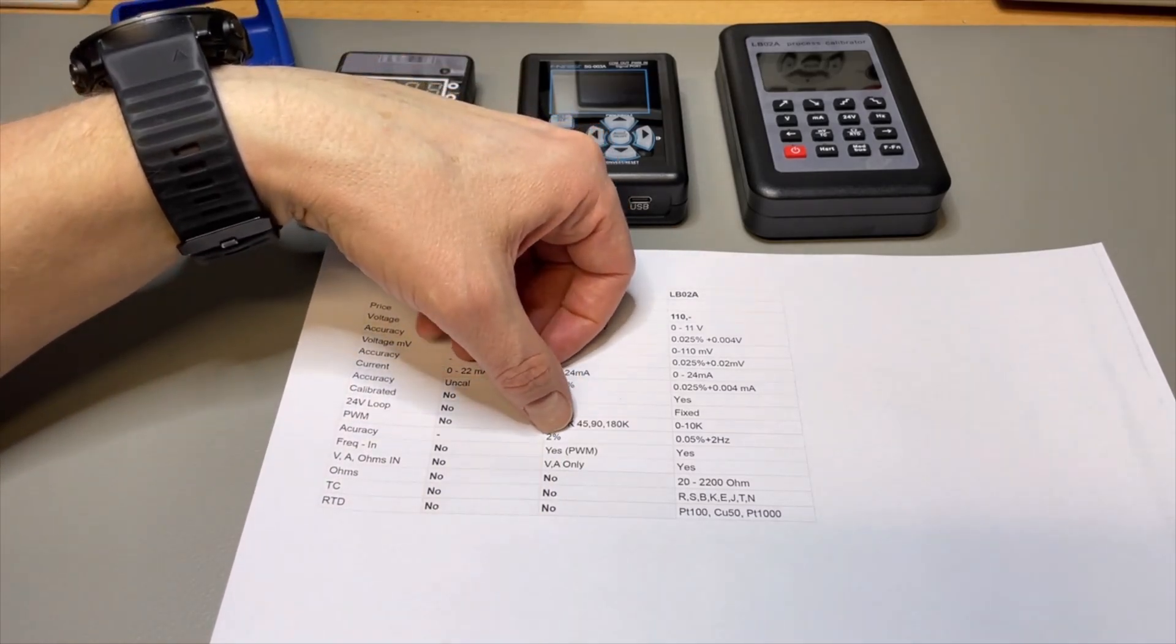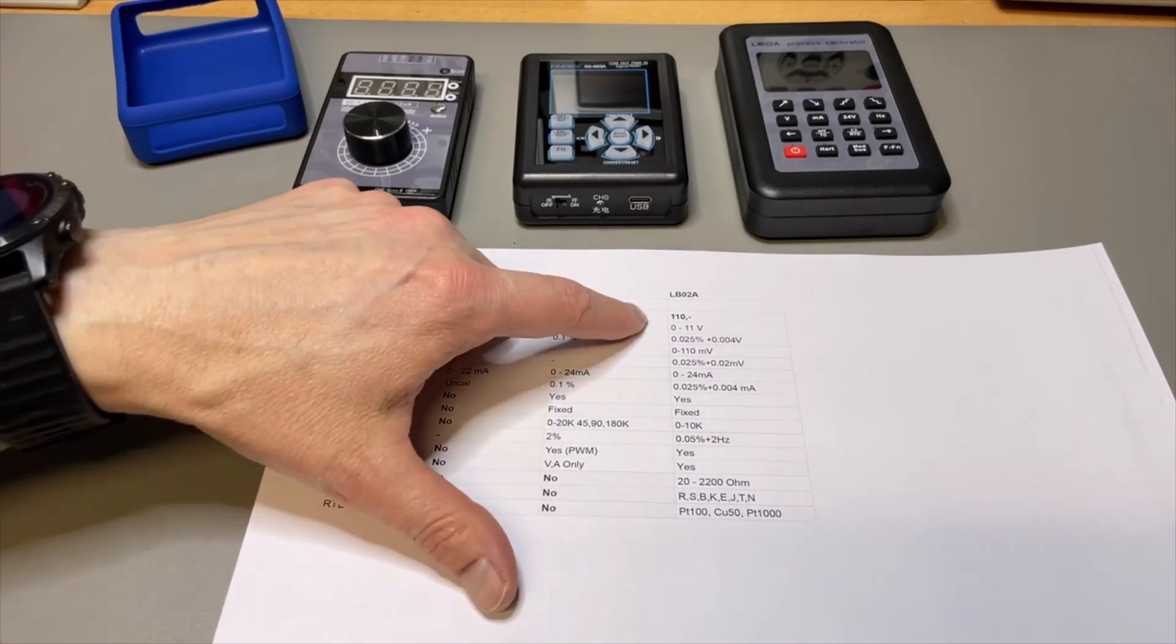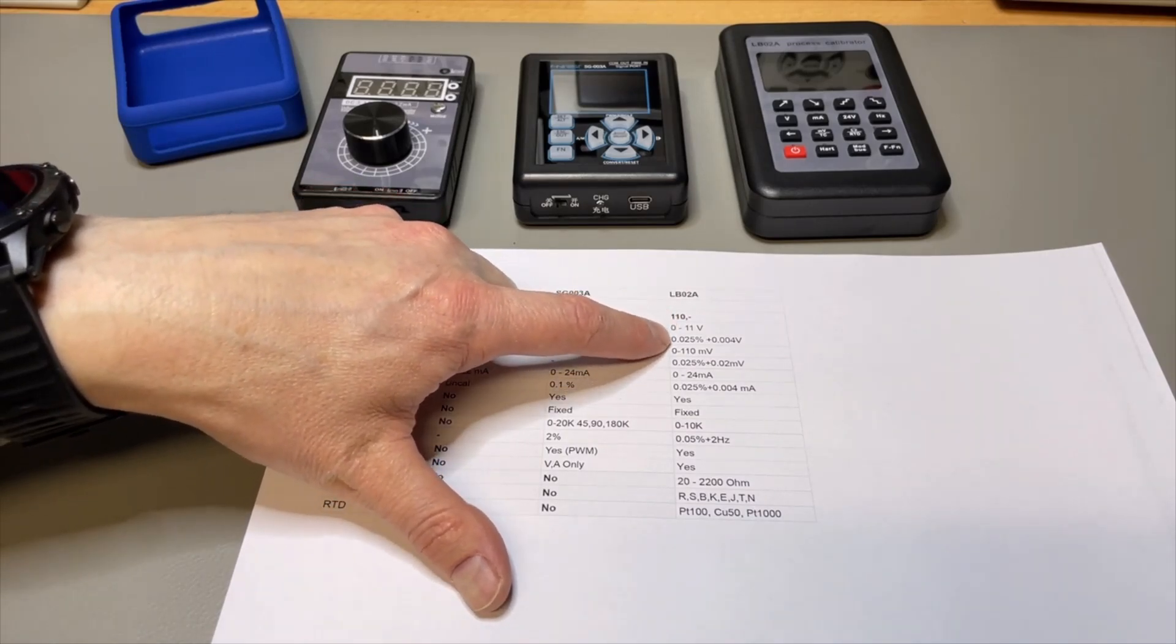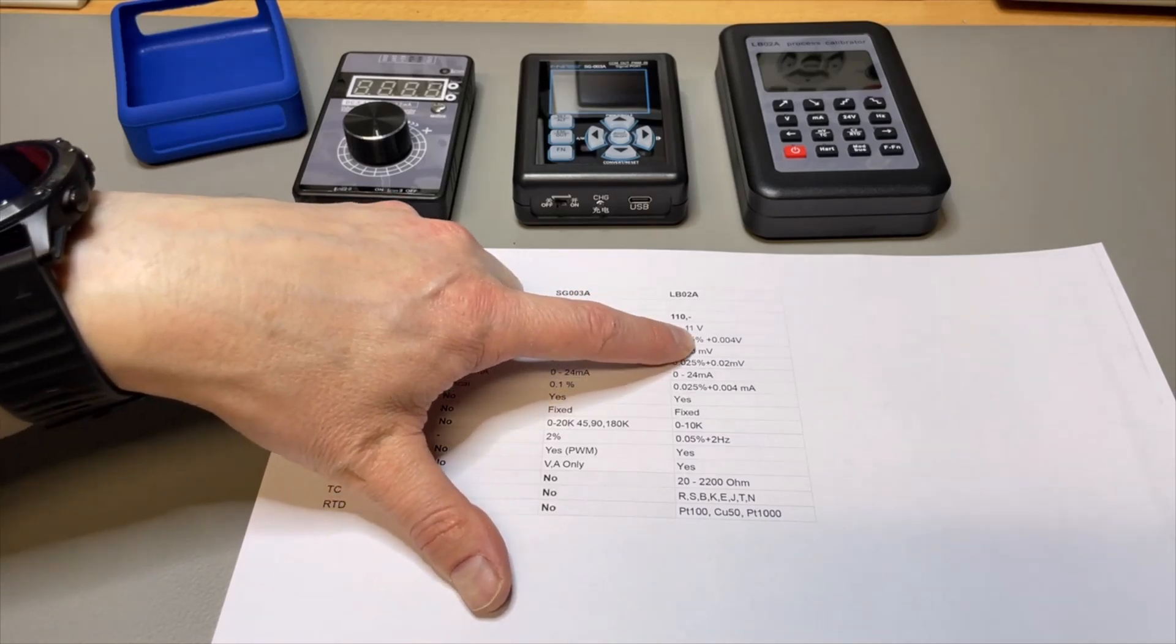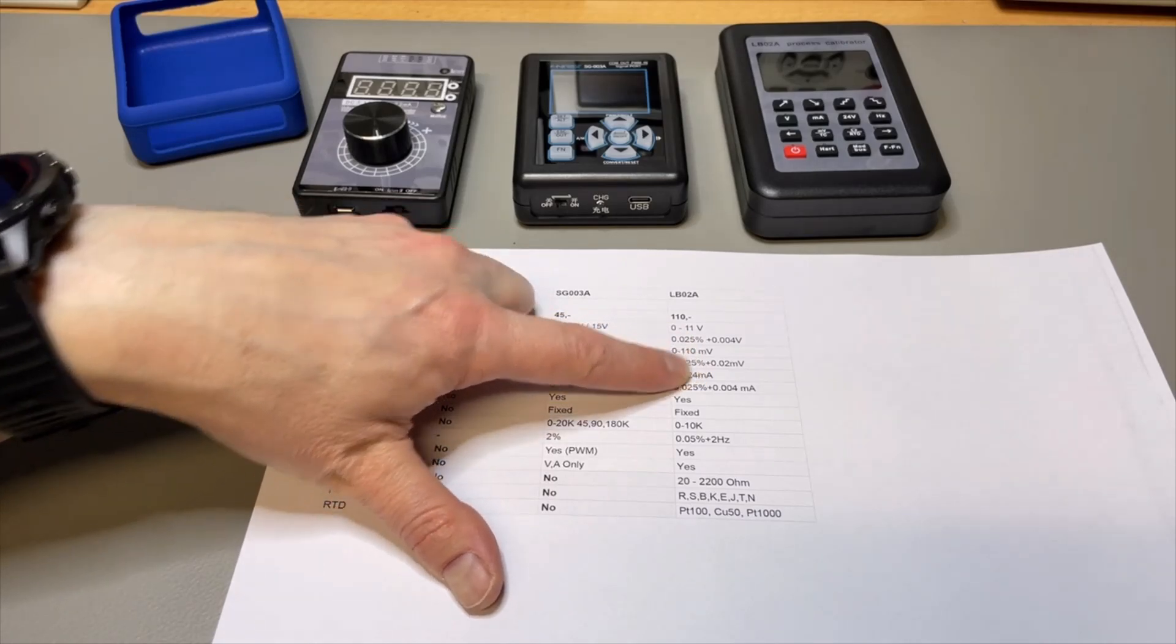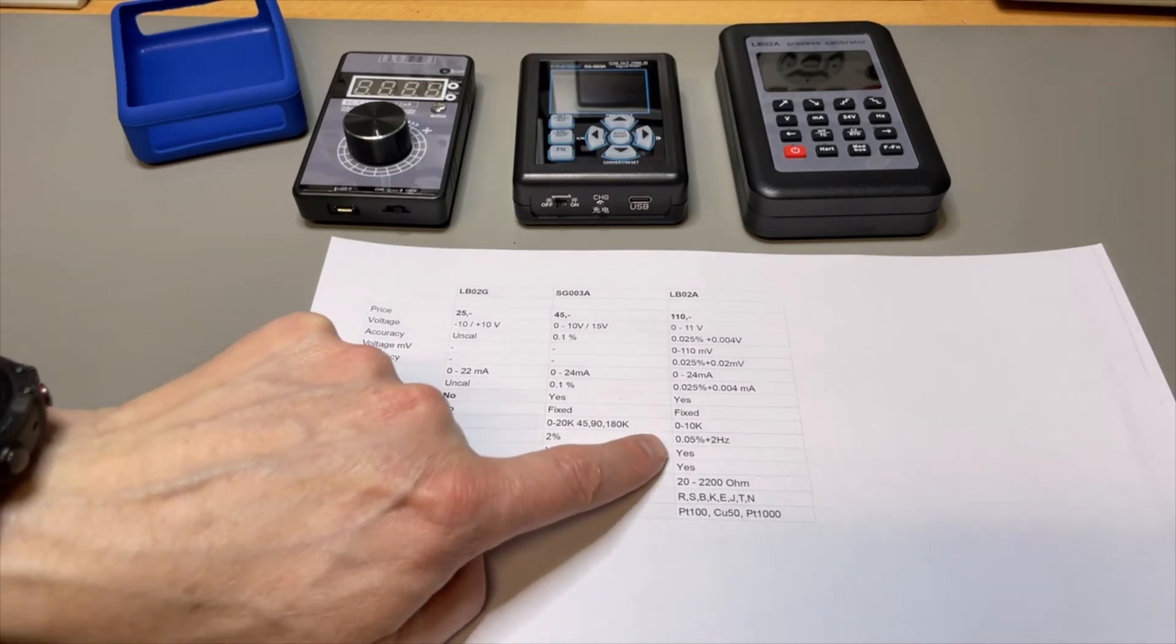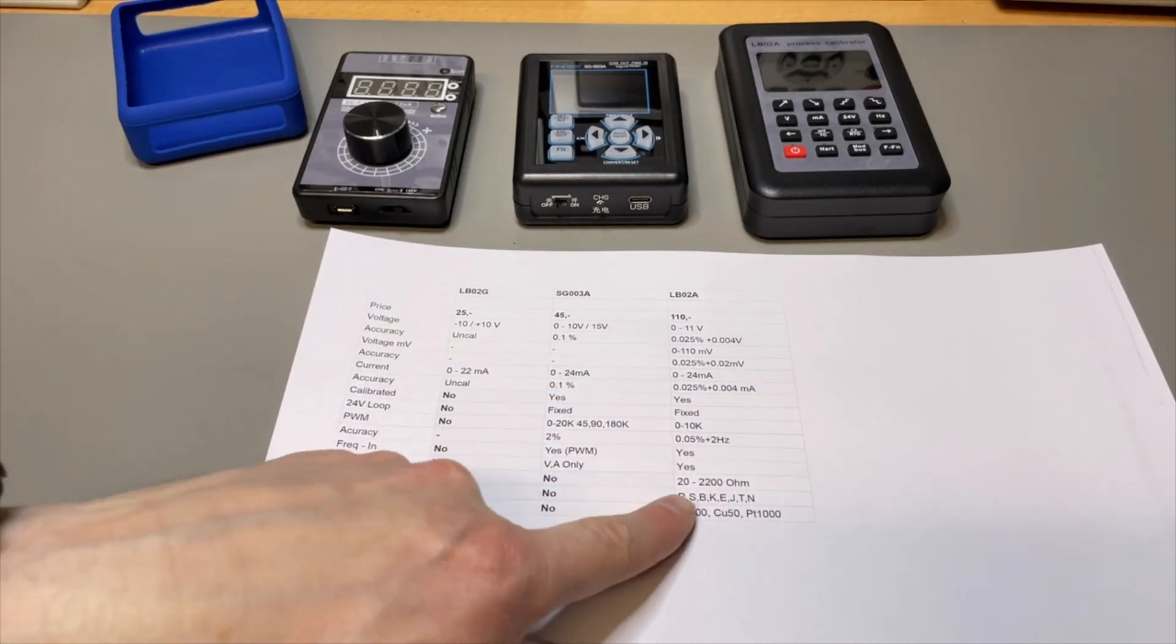As you can see that is only 2 percent accurate for the PWM function. You can even measure voltage and amps with it. If you want something better then it's this one, the LB02A. It can do 0 to 11 volts and it is 0.025 percent and it even has a millivolt setting as well. Current also. It comes calibrated. We saw that, it actually looked quite good. In the end the extra is all your temperature control and your ohms emulation.